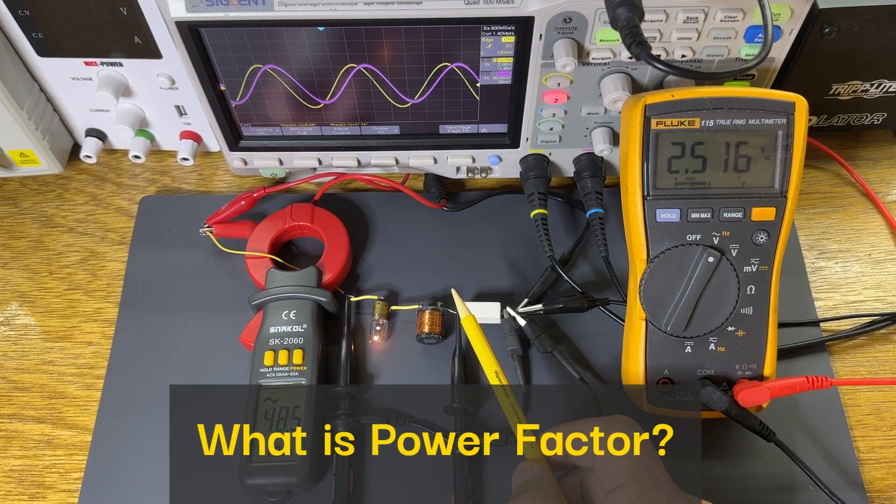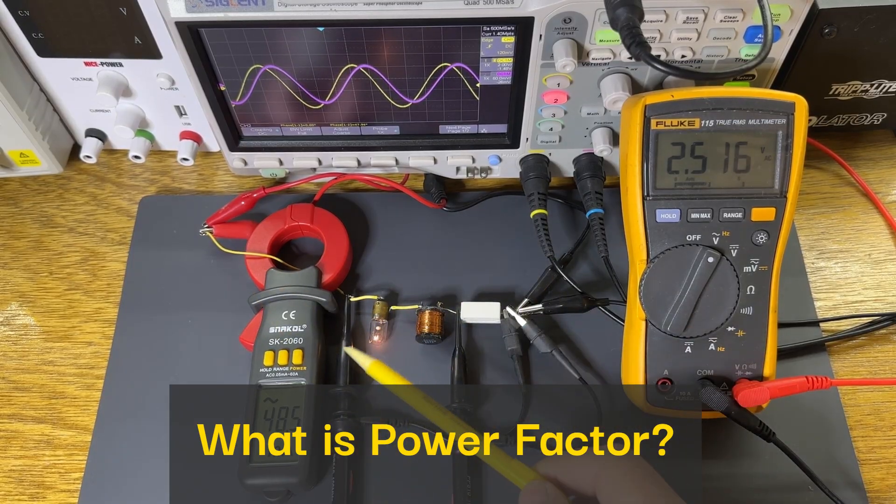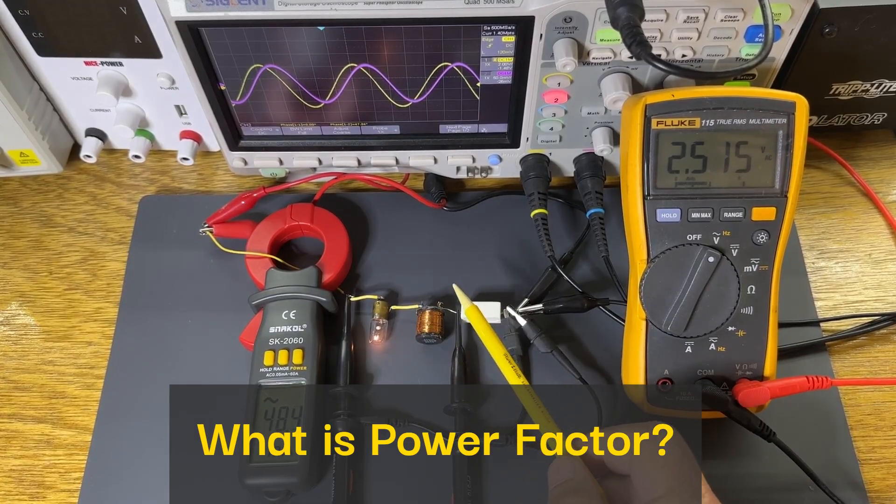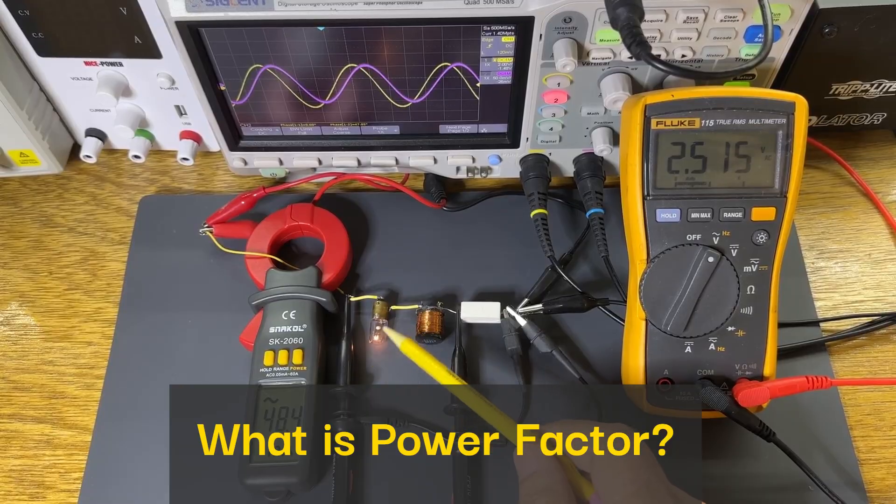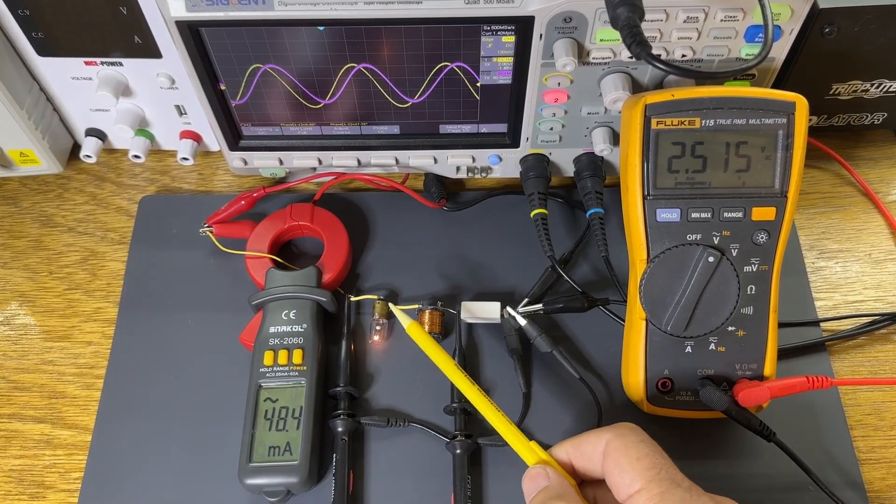So what is power factor? It is simply how much of the power that you draw from the supply actually does useful work. It is the ratio of real power to apparent power. In a perfect circuit, like a resistive light bulb, the current and voltage are perfectly in phase and the power factor is 1.0 or 100% efficient.